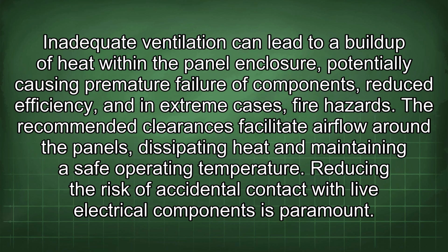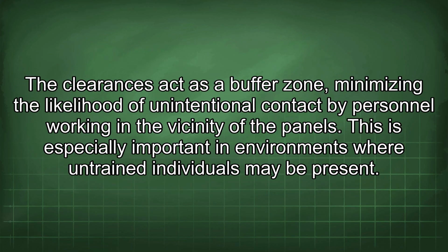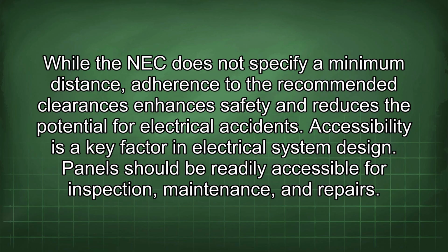Reducing the risk of accidental contact with live electrical components is paramount. The clearances act as a buffer zone, minimizing the likelihood of unintentional contact by personnel working in the vicinity of the panels. This is especially important in environments where untrained individuals may be present. While the NEC does not specify a minimum distance, adherence to the recommended clearances enhances safety and reduces the potential for electrical accidents.